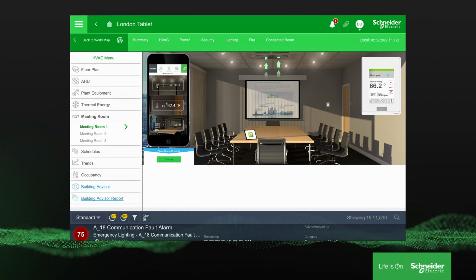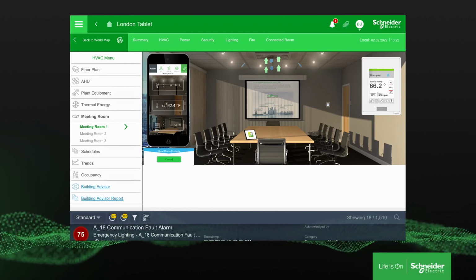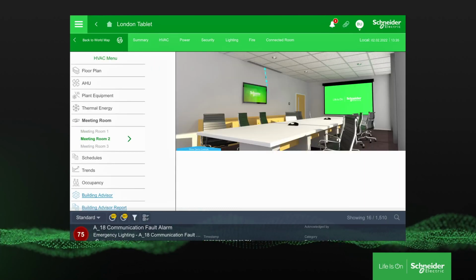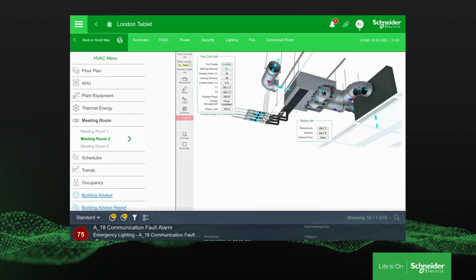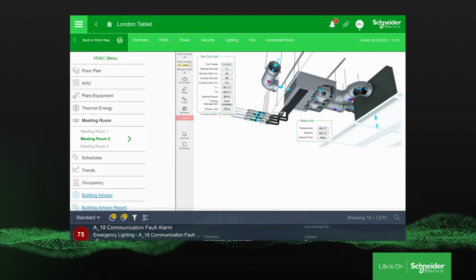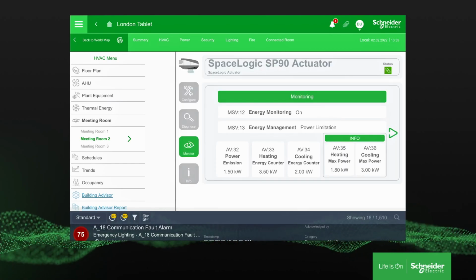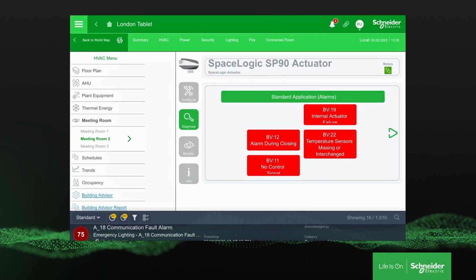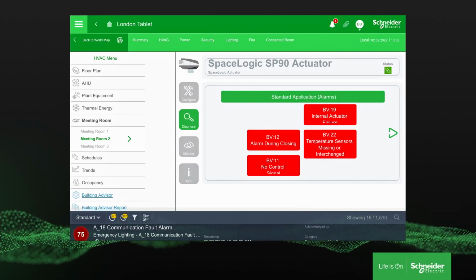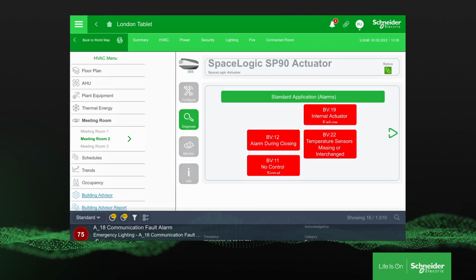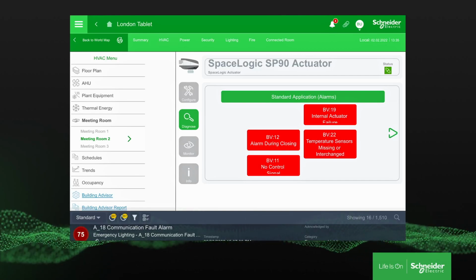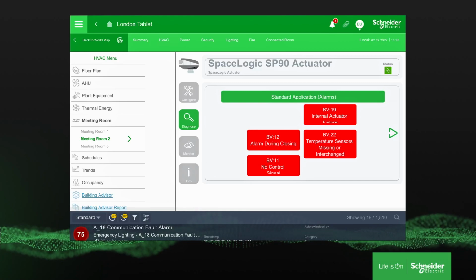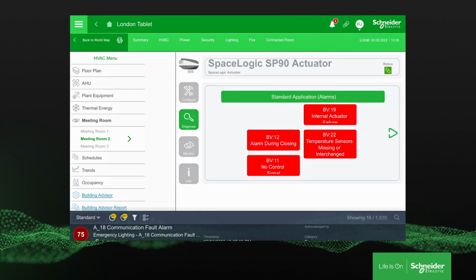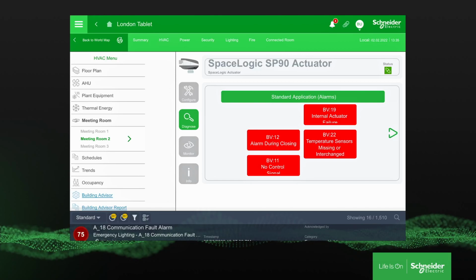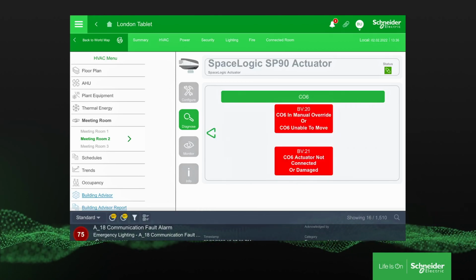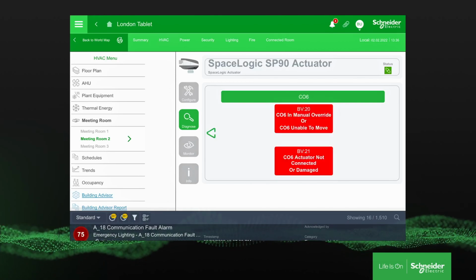Here I will use a tablet to adjust settings to my liking in this meeting room. This space is serviced by a fan coil unit with the new SmartX SP90 valves. They are top of the line, and when they were put into the system, we also had special diagnostic screens added to help us troubleshoot any issues that might arise. There is definitely a problem with the calibration. I need to send out the mechanic on this and remind them of the new calibration and recording process. After recording the valve serial number, I can shift back over to some of the other chores for the day.